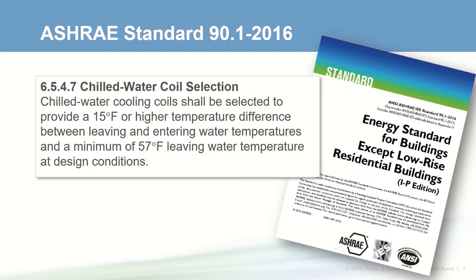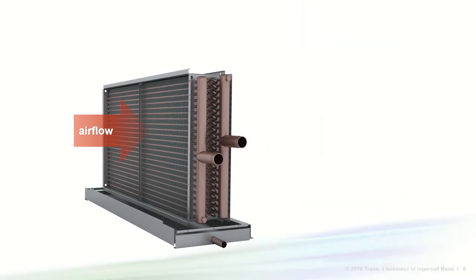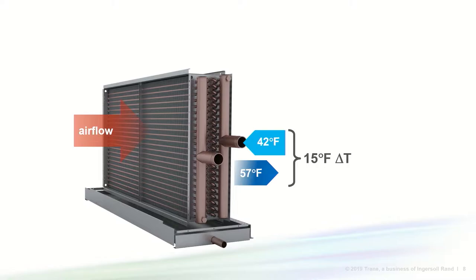Beginning in its 2016 version, ASHRAE Standard 90.1, the energy standard, now requires chilled water cooling coils to be designed for at least a 15 degree temperature difference between the leaving and entering water, and the leaving water temperature must be no colder than 57 degrees at design conditions. For example, in order for the leaving water temperature to be 57, a coil designed for 42 degree entering chilled water would comply with the minimum 15 degree delta T requirement.